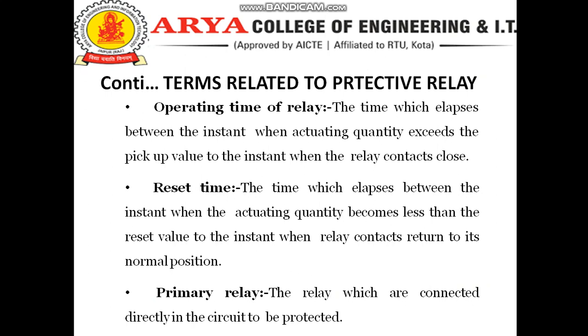Operating time of relay. The time which elapses between the instant when the actuating quantity exceeds the pickup value to the instant when the relay contacts close. Reset time. The time which elapses between the instant when the actuating quantity becomes less than the reset value to the instant when the relay contacts return to their normal position.